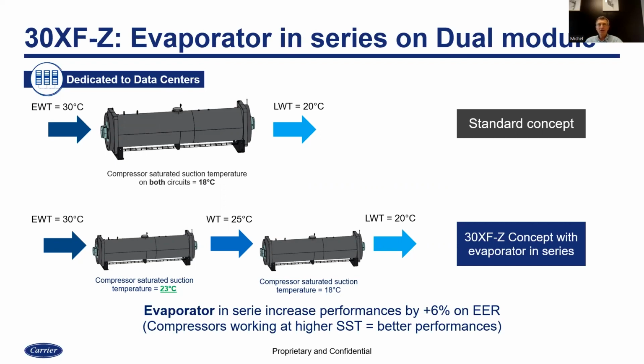So it seems to be kind of obvious. It's not, because there is a very significant difference between putting two evaporators in series or in parallel. If you put them in series, then the first evaporator will benefit from higher leaving water temperature than the final one. And you probably know that the higher leaving water temperature you may have in your system, the higher efficiency the system will have. So by putting the units in series in this specific way, we can benefit in this upstream unit from about 5-6% efficiency improvement without any improvement on compressor, heat transfer, etc. So this is purely system architecture. And this is something which is very important.